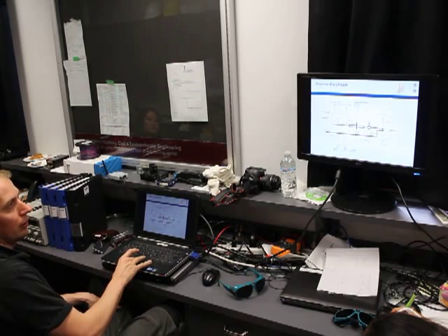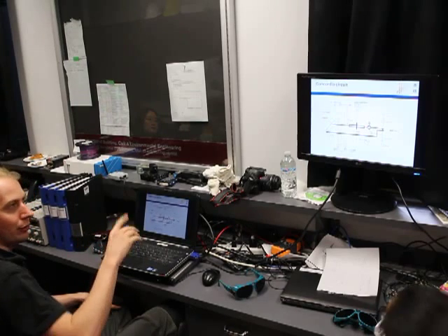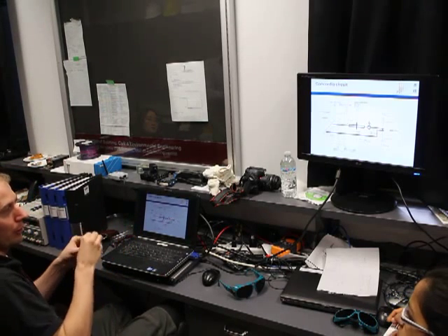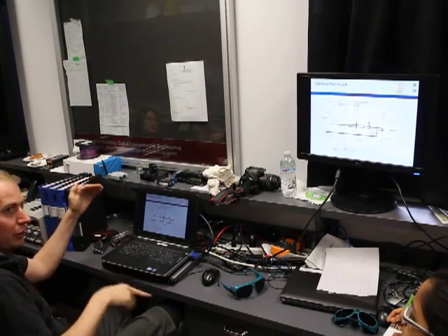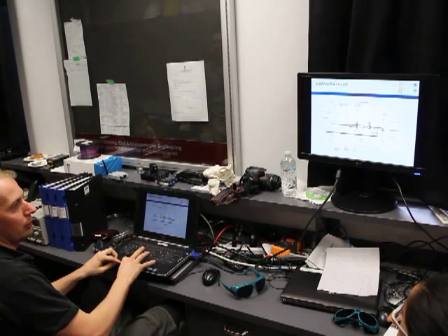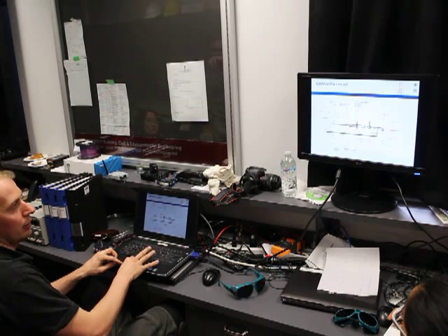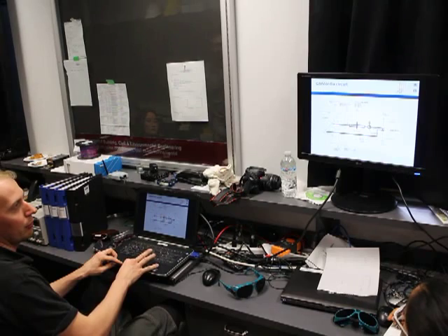You see, in order to always know the pressure of every point of the circuit relative to the pressure in the room, we reference all of them to this room pressure. So this is connected in order to know what the reference to the inlet is and what the reference to the outlet is, and the same is true here for the mass flow.